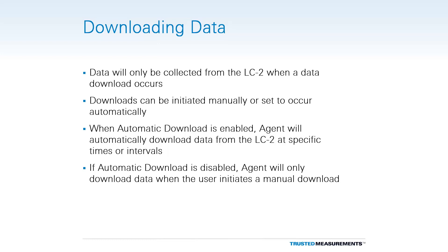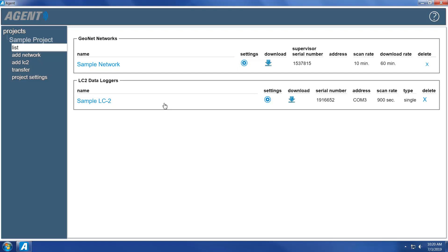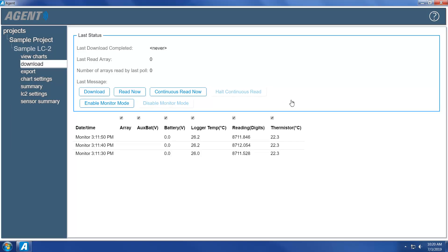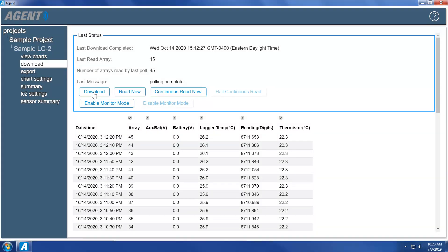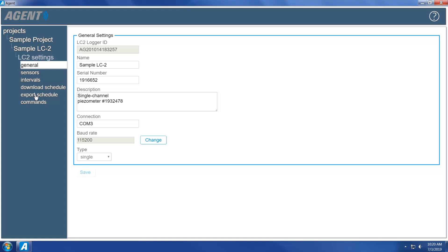Data will only be collected from the LC2 when a data download occurs. Downloads can be initiated manually or set to occur automatically. When Automatic Download is enabled, Agent will automatically download data from the LC2 at specified times or intervals. If Automatic Download is disabled, Agent will only download data when the user initiates a manual download. To perform an immediate one-time download, click on the blue Download arrow. Agent will navigate to the Download screen. Click the Download button to begin downloading — Agent will download all new data collected since the previous download. To enable Automatic Download, navigate to the LC2 settings, then click Download Schedule on the left side of the screen.